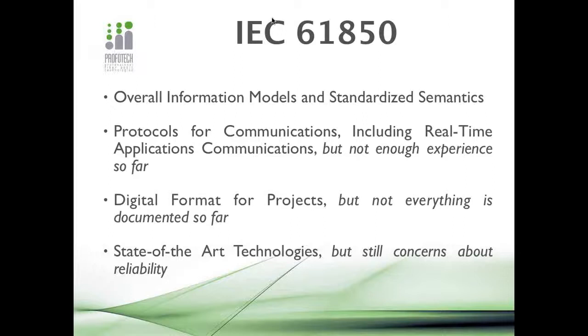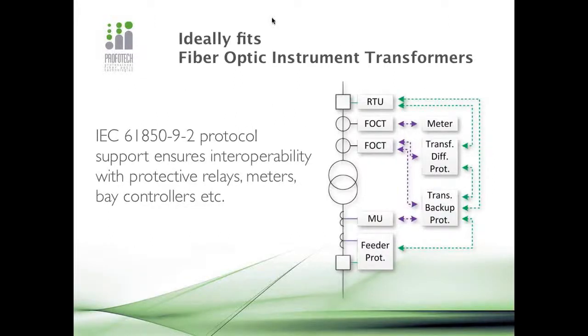And finally, this standard enables us with communications using the state-of-the-art technologies. Of course, I'm speaking about the communication technologies first of all. But still, there are concerns about the reliability of these projects. IEC 61850 ideally fits fiber optic instrument transformers, and that is what I would like to show using this slide. Unfortunately I cannot use my mouse, but to the right you can see the picture, and we can see the FOCT, which stands for fiber optic current transformer. There are two of them. We can see meter, transformer and differential protection, transformer backup protection.